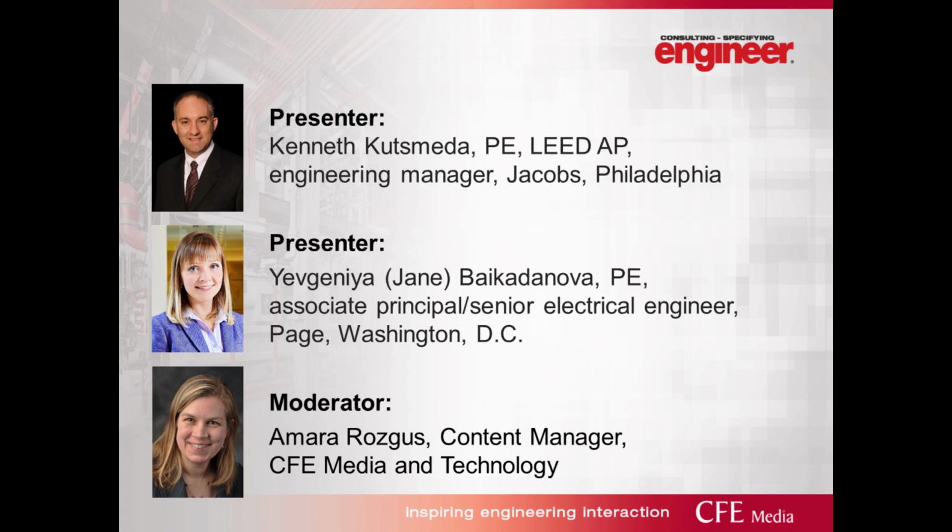It can also be used on the utility side, but you do have to be careful when you get down into the systems, with things that are grounded and ungrounded, that you maintain that same resistance throughout. But it's definitely, I would say, an advantage of using it on medium voltage generators.